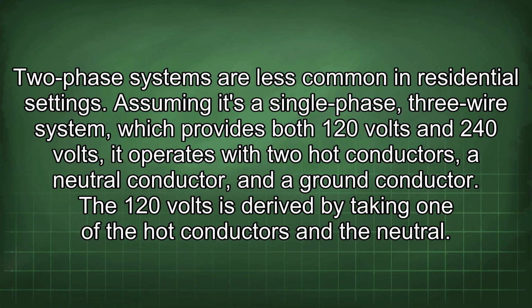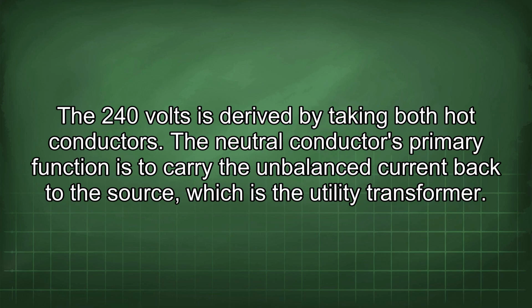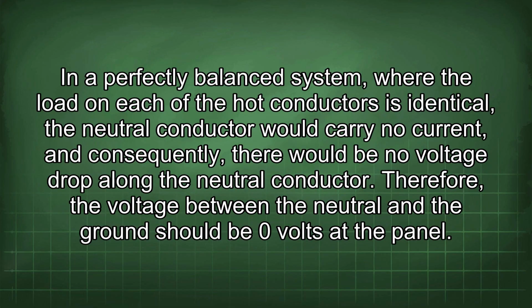The 120 volts is derived by taking one of the hot conductors and the neutral. The 240 volts is derived by taking both hot conductors. The neutral conductor's primary function is to carry the unbalanced current back to the source, which is the utility transformer. In a perfectly balanced system, where the load on each of the hot conductors is identical, the neutral conductor would carry no current, and consequently, there would be no voltage drop along the neutral conductor. Therefore, the voltage between the neutral and the ground should be 0 volts at the panel.